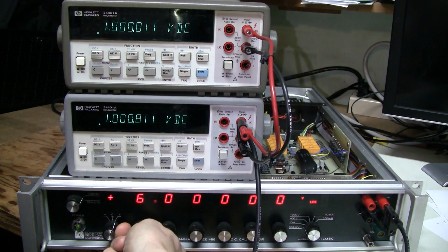And let's go to 10 volts. Wait for meters to settle. There you go. And in this range the meters disagree by about 5 ppm. And the calibrator is out by about 540 ppm. So I'm quite happy that meters agree this closely, and strictly speaking such comparisons don't mean much, because you never know, the meters could have drifted the same way, but still I think it helps to build up confidence in my meter. So let's assume my meter is perfect and go through the calibration procedure.